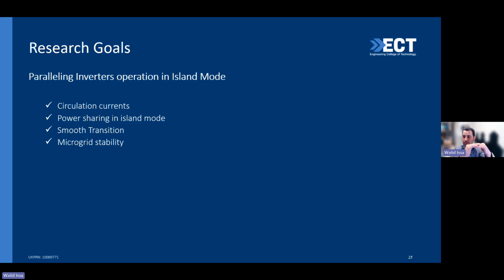For example, if I am in grid-connected mode and want to move to island mode, or vice versa, how smooth is that transition? Sometimes when you close that switch, a lot of inrush current might happen and damage the system. So I want to ensure this happens smoothly, and also ensure the stability of the microgrid.